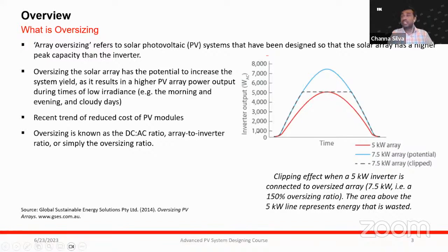Let's look at this in very simple terms without considering any technical specification. We normally oversize PV arrays and inverters by looking at the module price. When comparing the global market, solar module prices are sometimes cheaper, so in that period we can buy additional modules to get a much higher return, because everything after the inverter becomes fixed cost, and the only variable cost is what's connected before the inverter. So if that segment is cheaper, it makes sense to add more to get a higher energy yield. Let's look at later slides for what else you need to consider.